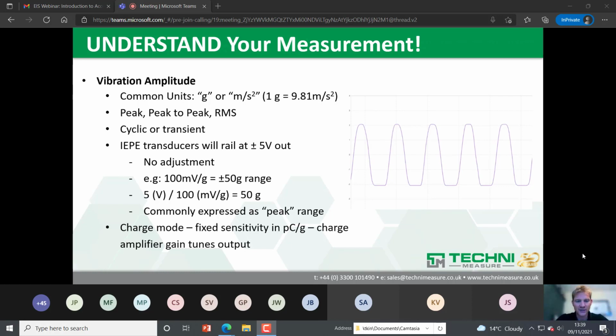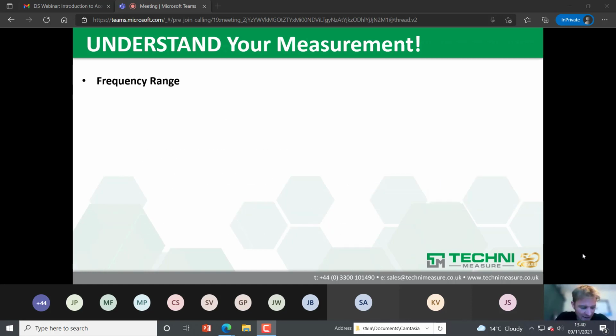Charge mode, as Keith mentioned, these have a fixed sensitivity output in picocoulomb per G, and you actually tune the final voltage output using the gain of your charge amplifier. So again, if you're using a benchtop charge amplifier with adjustable gain, then happy days, you can just tweak the knob down if you find you are railing. But if you've got an inline charge amplifier, that's likely to have a fixed gain. So you just have to make sure that you've chosen the right gain of charge amplifier to make sure you don't rail your measurement. You've got enough headroom in there to capture the full vibration amplitude that you're trying to measure. The next most important thing about vibration measurement is obviously the frequency range.